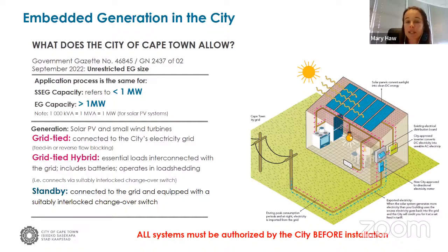When we talk about SSEG, or small scale embedded generation, we're typically talking about systems smaller than 1 megawatt or 1 MVA. Systems bigger than that are typically embedded generation capacity. The different system types are grid-tied systems, directly connected to the city's network with or without reverse flow blocking, allowing you to feed into the system or not, and grid-tied hybrid systems, similar but with a battery connected, which can operate during load shedding.